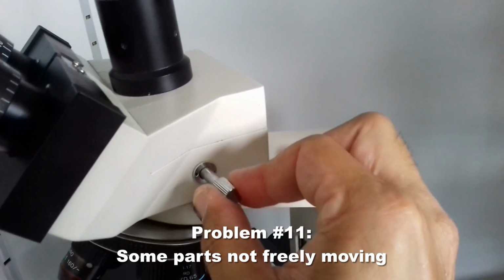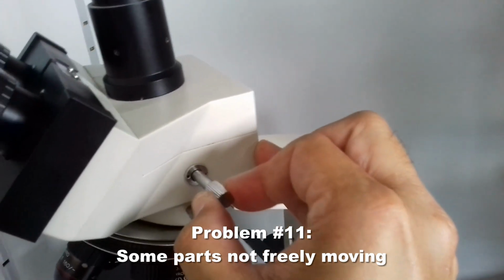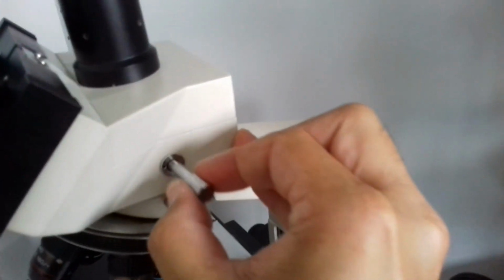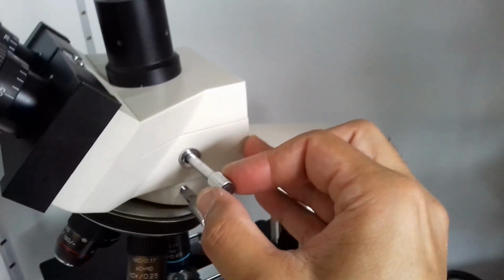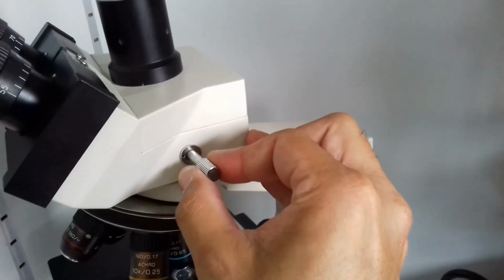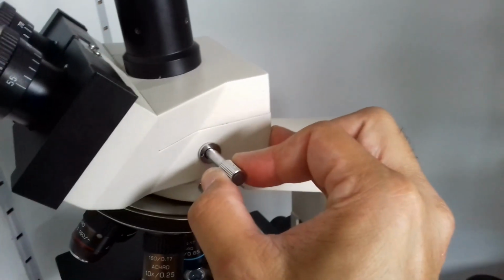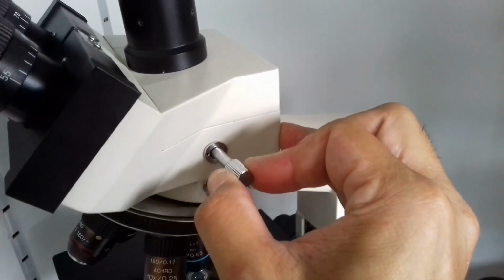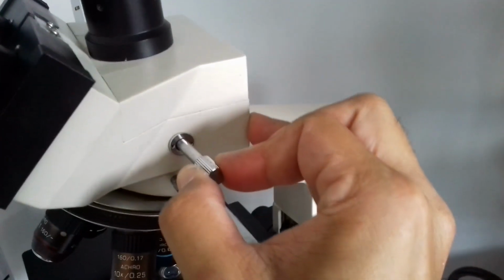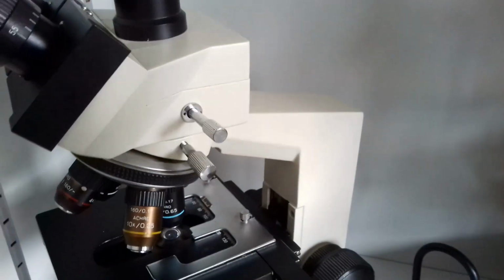One of the microscopes that we had there had a trinocular head for photography, and it was practically very rarely used, but there is a little lever that you can push in and out, and this lever is there to redirect the light to the phototube, and it was scratching. So it was not moving smoothly, there was some kind of abrasion inside the microscope head. So this means that this was also not manufactured according to proper tolerances.